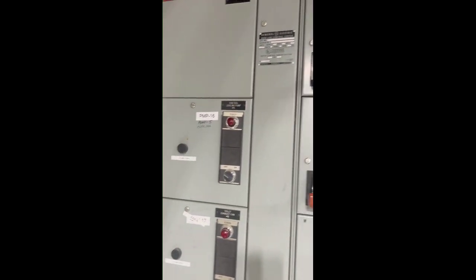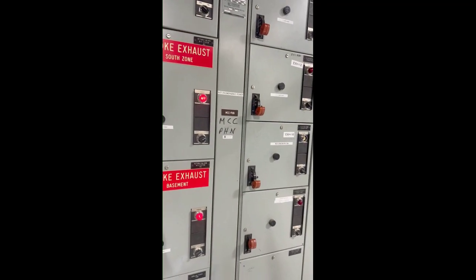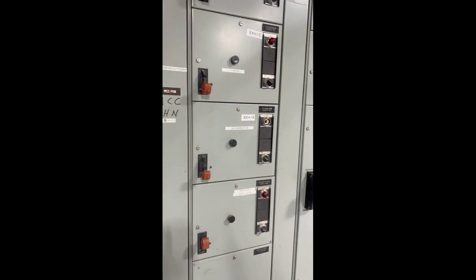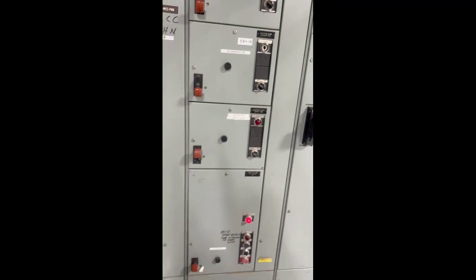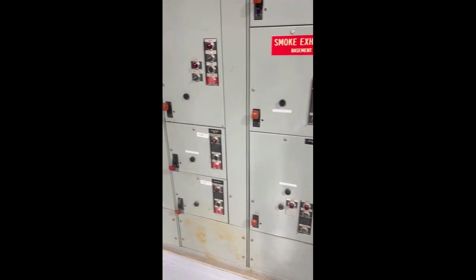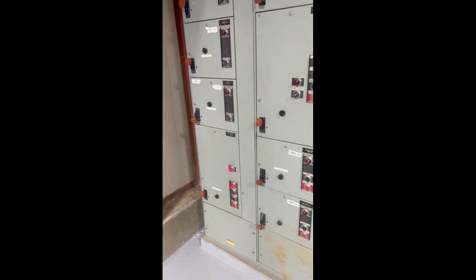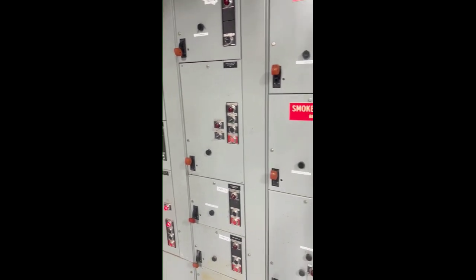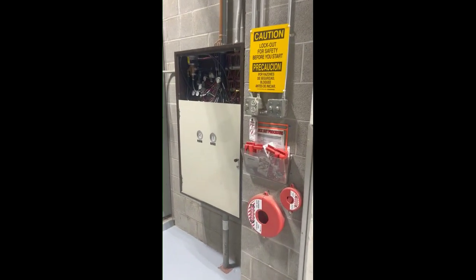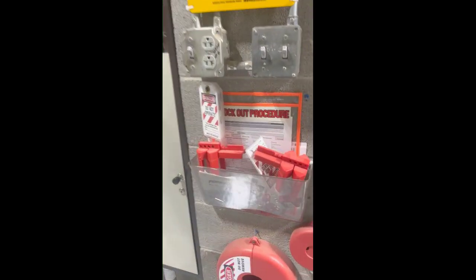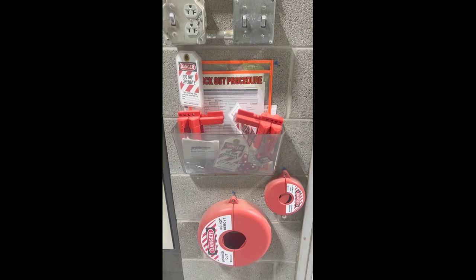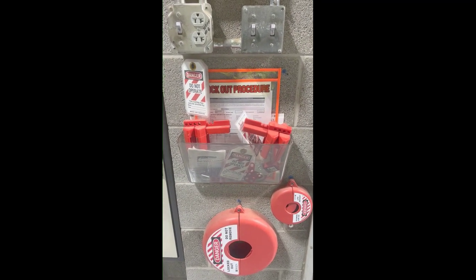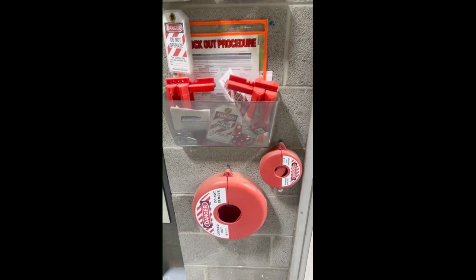Everything here looks to be normal in what's called an MCC bucket array. This is an MCC bucket. Long term, it's called Motor Control Center. This is what makes all my equipment run. These are the starter contactors that will energize the circuits to make stuff run in this plant. Also noting the proper lockout tagout kit, as well as the procedures and the logs and everything that goes with it.